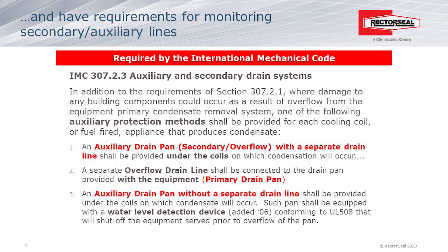From the 2018 IMC code commentary: an auxiliary redundant drain pan or secondary drain is required for equipment locations where condensate overflow would cause damage to the building. The purpose of the auxiliary drain pan and secondary drain is to catch condensate spilling from the primary condensate removal system, protecting the building from structural and finished damage — not building contents such as storage. Condensate drains are notorious for clogging due to debris, lint, dust, and bio growths in drain pans and pipes. This section lists four options for preventing damage where the equipment is located in attics, above suspended ceilings, furred spaces, and upper stories, and one of the four methods must be used.